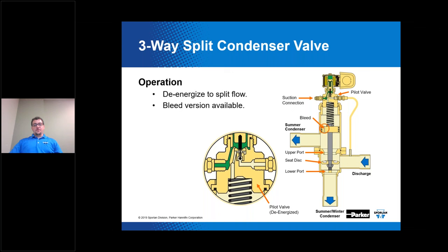When de-energized, the three-way split condenser valve diverts or splits refrigerant flow to two condenser circuits during summer operation — this is considered normal full condenser mode. The refrigerant flow is split evenly between the two halves of the condenser; the seat disk is positioned to allow the flow of discharge gas through both the upper and lower port simultaneously. When you energize the valve, it shifts and diverts all flow to only the summer/winter condenser, closing off the upper port so all flow goes to that single circuit during low ambient operation.